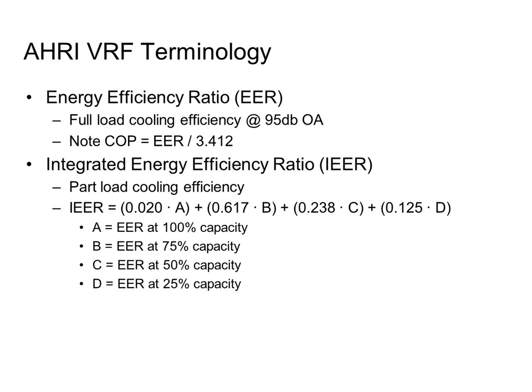The chiller and condensing unit guys do it similarly. I think the weightings are slightly different, but they test them in those 4 buckets, 25, 50, 75, and 100, to get you a part load efficiency rating. If you do anything with utility programs, not necessarily VRF, but just in general, like chillers and stuff like that, you'll notice that most of the utility programs don't even look at EER. They simply specify IEER, because part load is where the action is at. EER is somewhat irrelevant because it's never really a full load day in most cases.